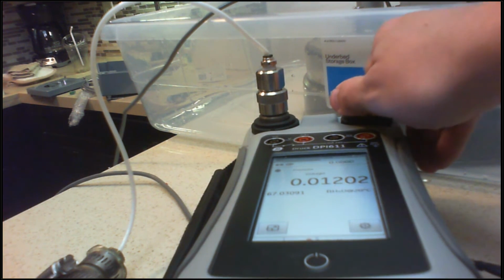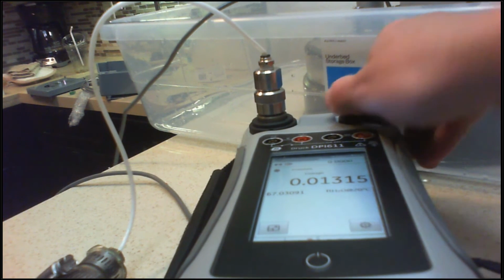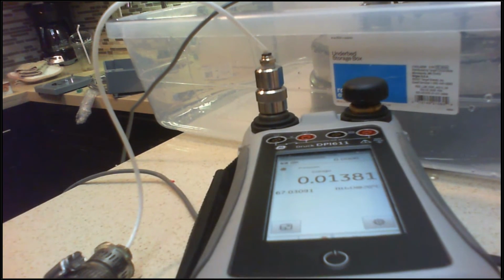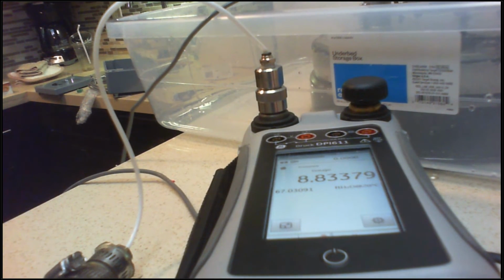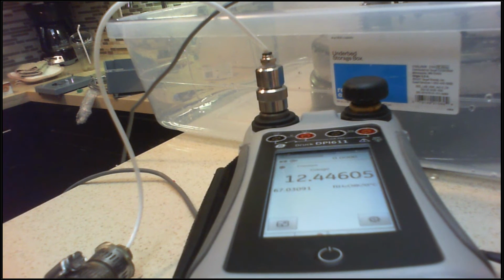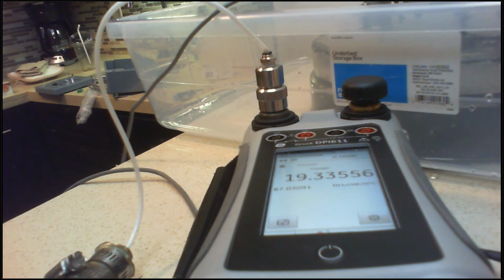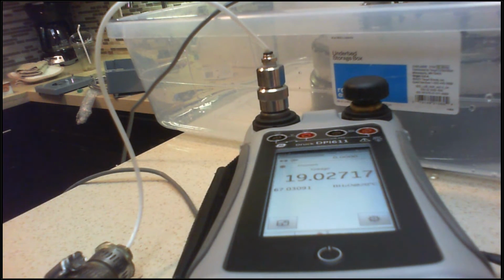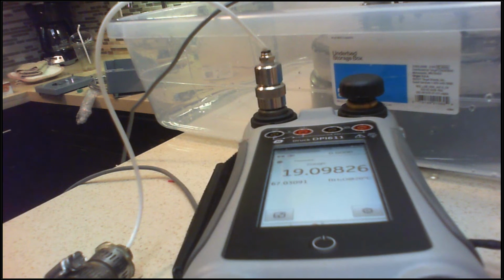Now I'm going to close this off, and I'm going to apply pressure. And I'm going to go up to about 20 feet or so. I don't have a great seal right now, probably because it's been on it for about an hour, and I'm in my hotel room. But you can see that PT is dropping by about 1/10 of a foot a second or so.